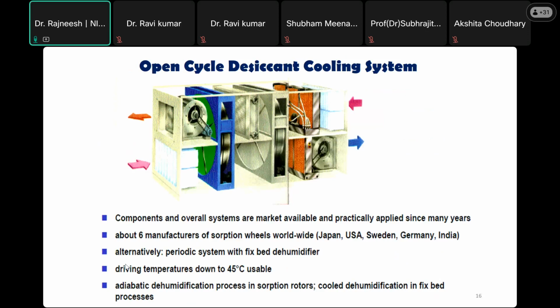Alternatively, periodic systems with fixed bed dehumidifiers are also available, with driving temperature less than 45 degrees C. We can work with these cycles at this very low temperature, which can be used to regenerate the liquid desiccant material. The purpose is to regenerate the desiccant material, and if we have the regeneration temperature lower, it means the energy input is a little less.